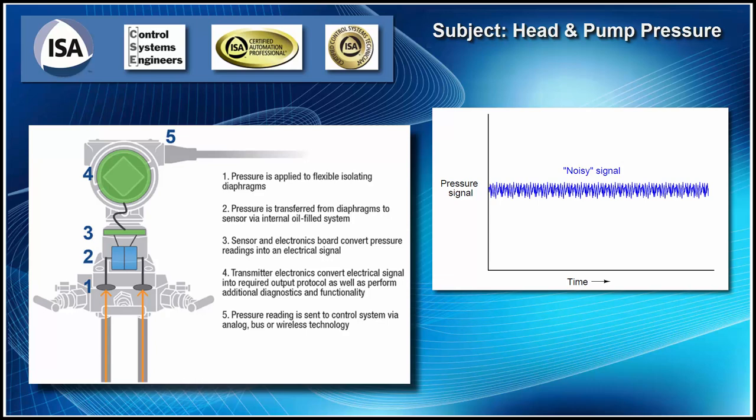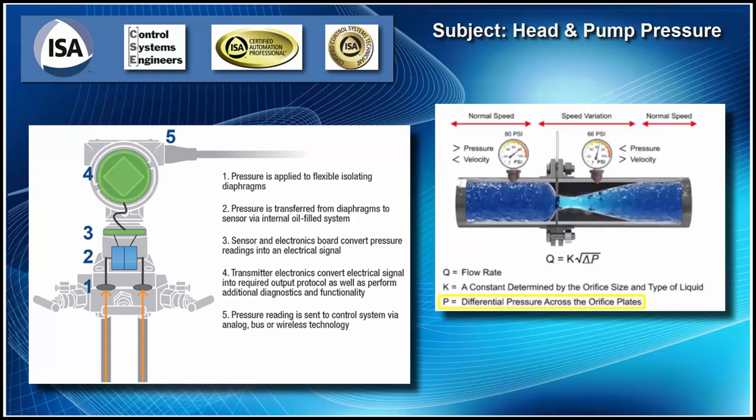So what you've got to understand is these columns of water going into these transmitters are constantly falling through the pipe, and the pump is accelerating it back up into the column. And so these columns vary up and down with your flow rate and pulsations of the pump. A transmitter will actually have pulsations, and this is where some of the noise in the transmitter comes from, because of the pump pulsations. We'll talk about how this works in process pipes after the break.